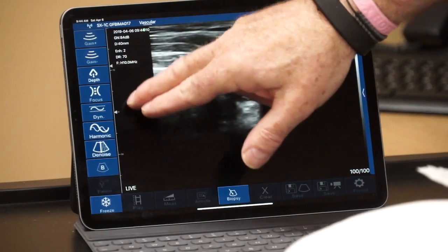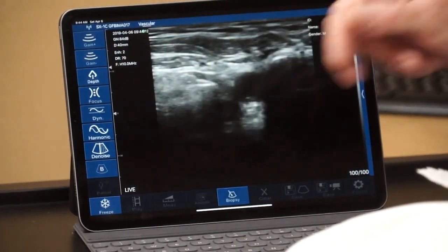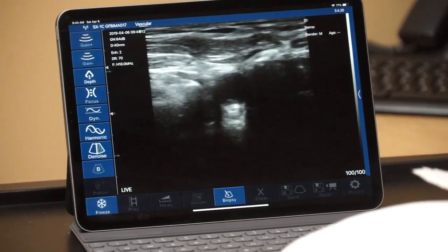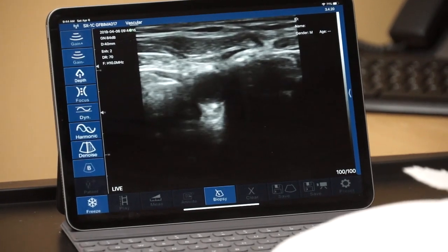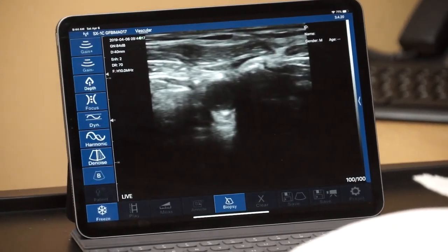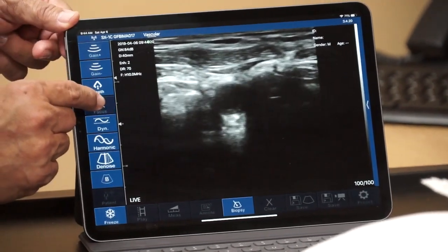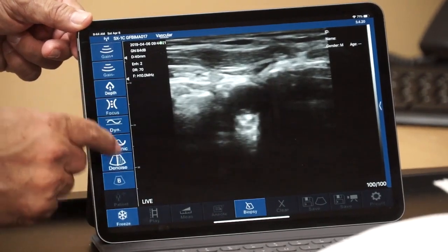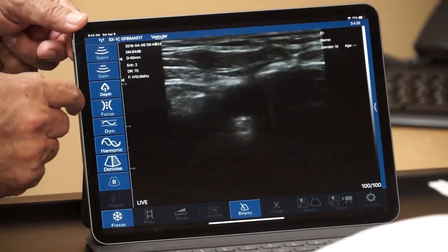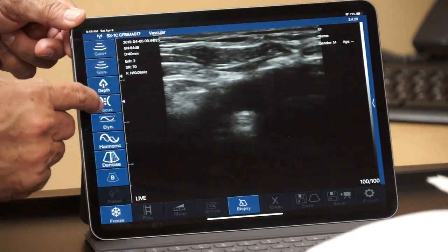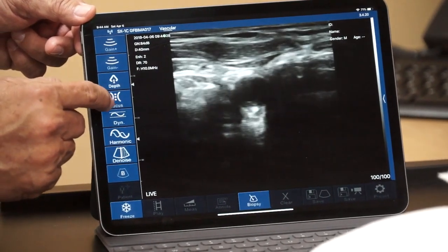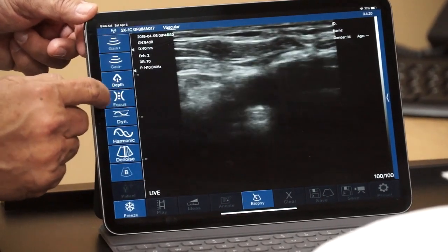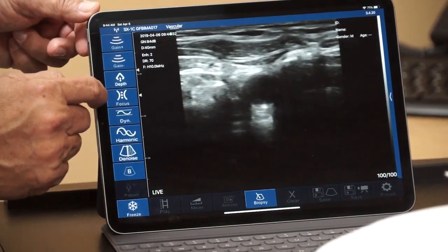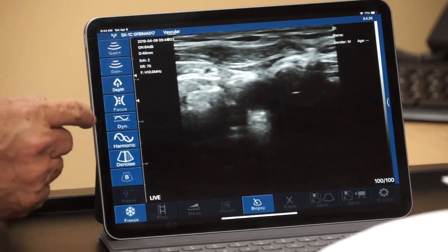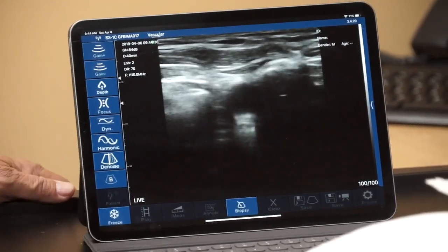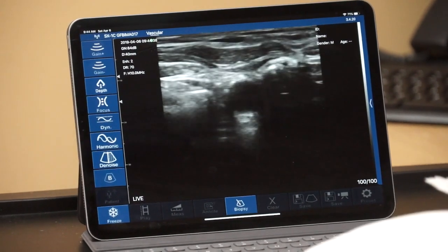This is the place on the viewing screen where the ultrasonic signal is best focused in intensity. That's controlled by the button labeled focus. If you watch closely, the arrows on the left side of the screen will change their position from superficial to deep, and the ultrasonographer or provider will choose the best location for those arrows based on the target of the image. The next button down is labeled DYN.